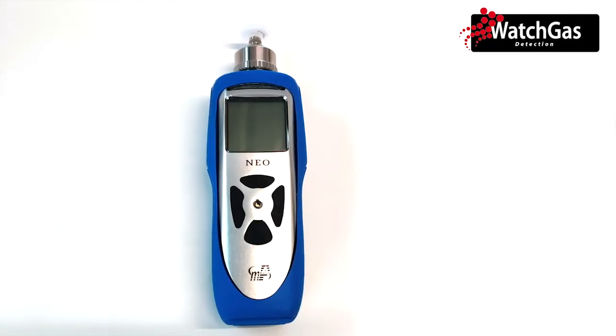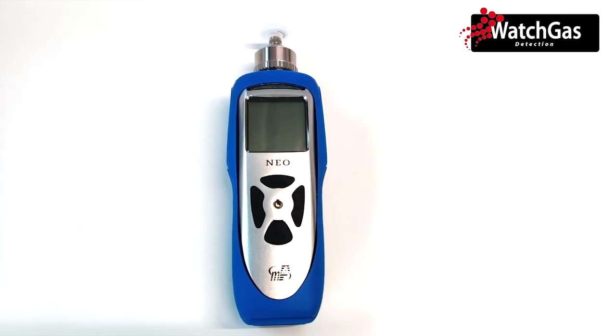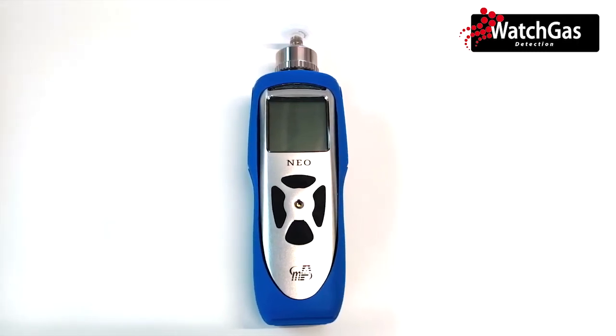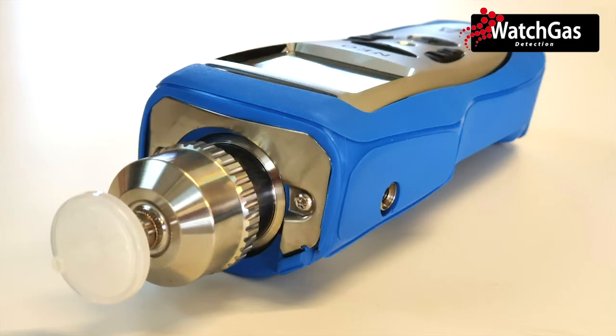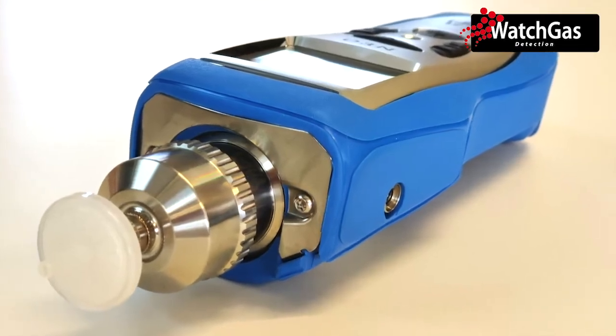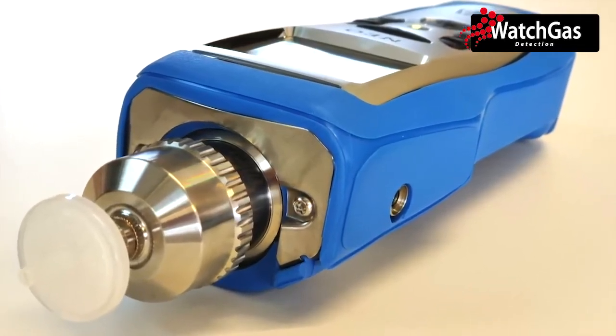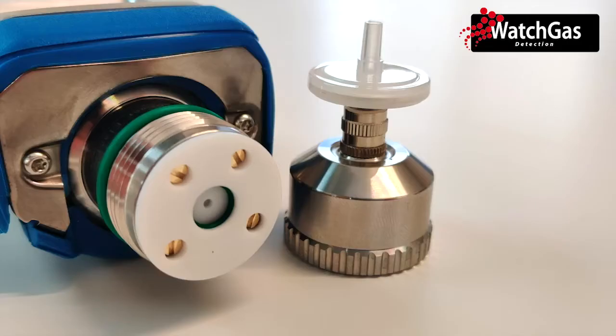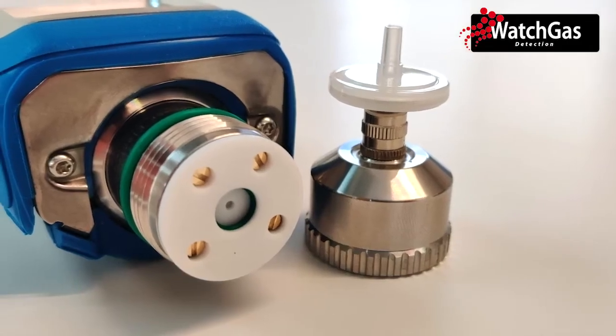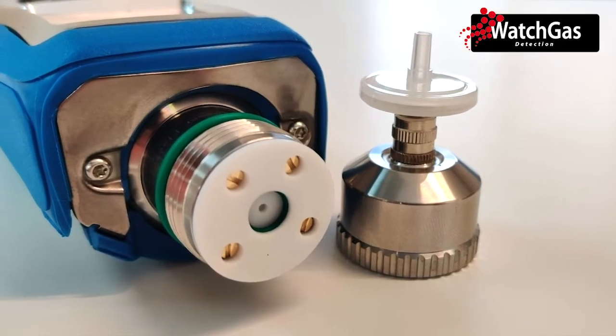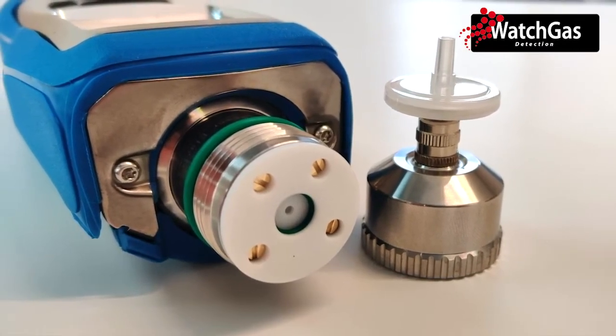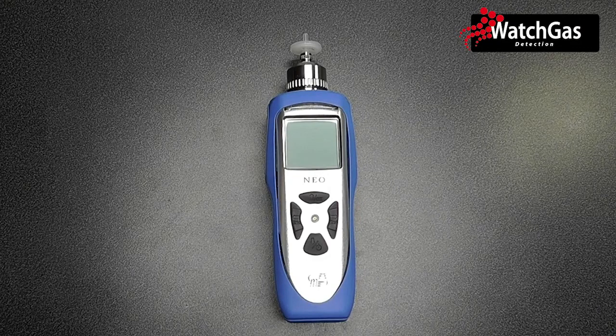The NEO comes in 4 different variants, available in ranges from 0.01 to 5000 ppm, 0.01 to 15,000 ppm, 1 ppb to 15,000 ppm, 0.05 to 10,000 ppm VOC, and 0.05 to 200 ppm benzene specific measurements. Here we happen to have the 0.01 to 15,000 ppm variant of the NEO. There are a variety of photoionisation detectors available on the market, available for detecting volatile organic compounds.